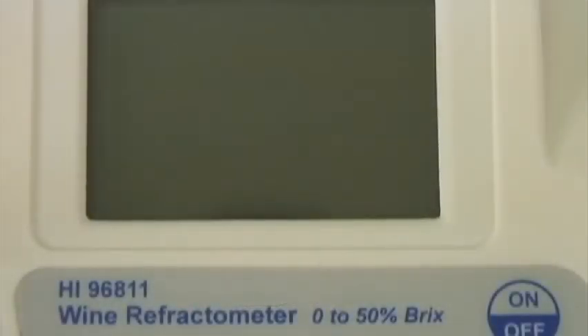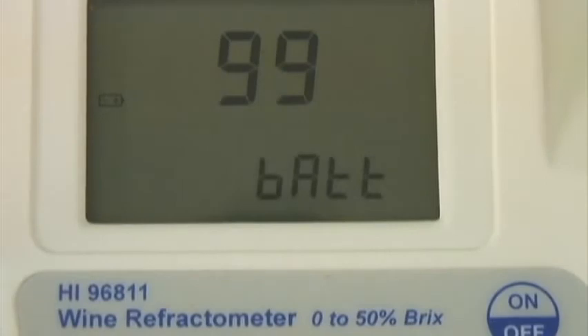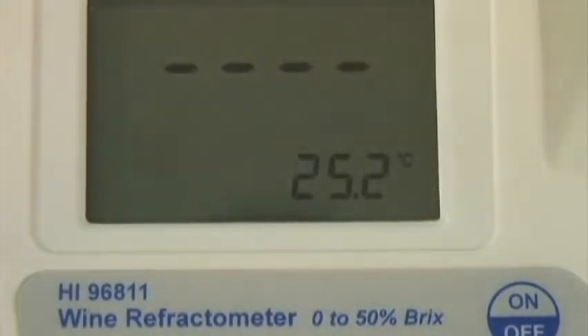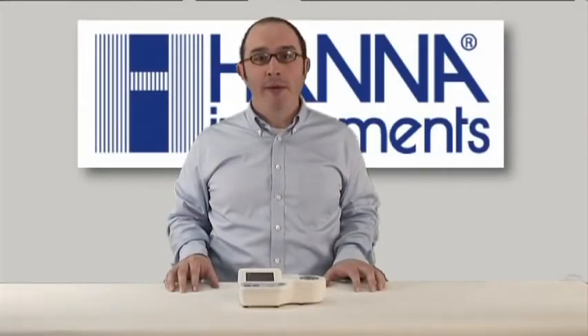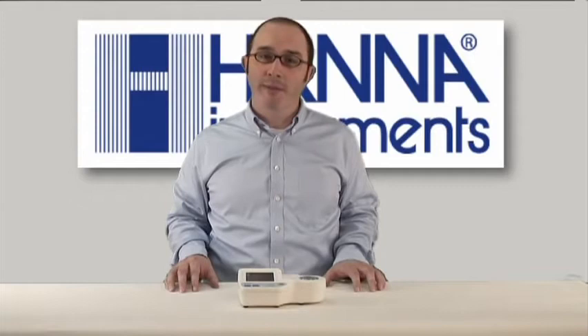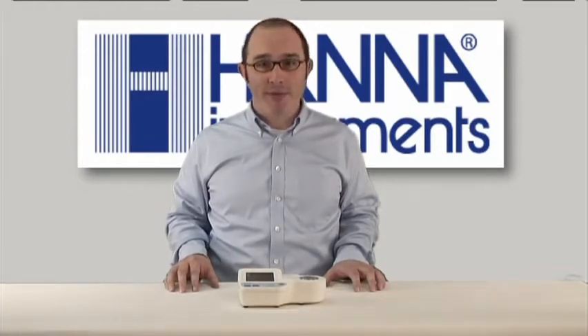Once you've inspected and set up your product, go ahead and turn on the refractometer. All of the LCD elements will be displayed, followed by the remaining battery life. When the LCD displays dashes, the instrument is ready for calibration. Calibrations should be performed daily before measurements are made, when the battery's been replaced, or between a long series of measurements. It's only 3 simple steps.